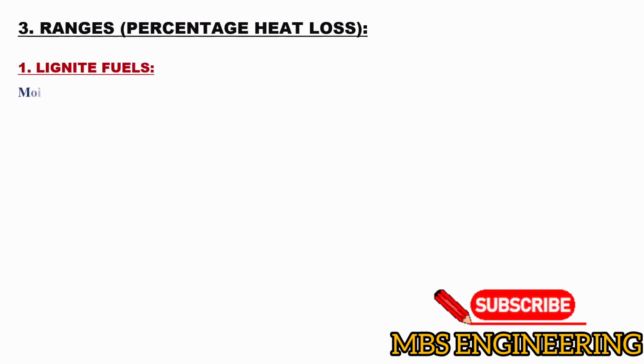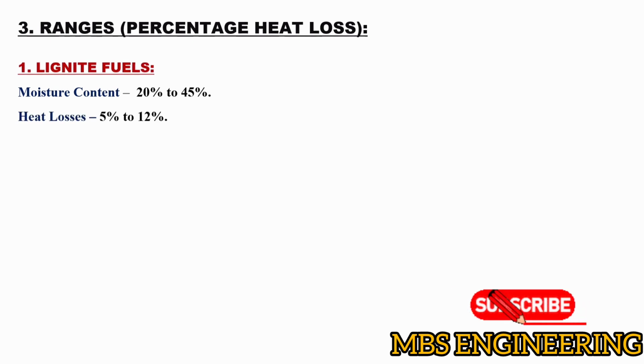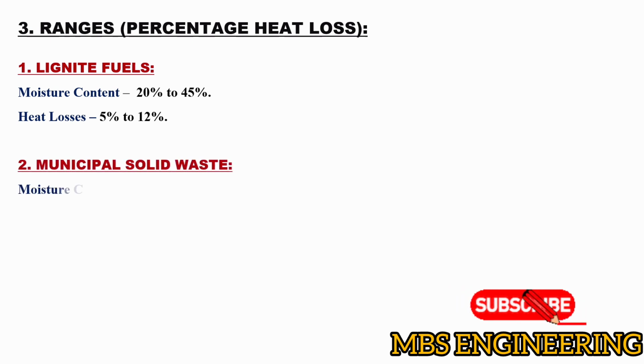Next, we will learn and understand the ranges of the percentage heat loss due to evaporation of moisture present in fuel in the boiler system. Let's look at how different fuels behave when it comes to moisture content and heat loss. In lignite fuels, the moisture content ranges from 20% to 45%, and the heat losses range from 5% to 12%. In municipal solid waste, the moisture content ranges from 25% to 50%, and the heat losses range from 8% to 15%.